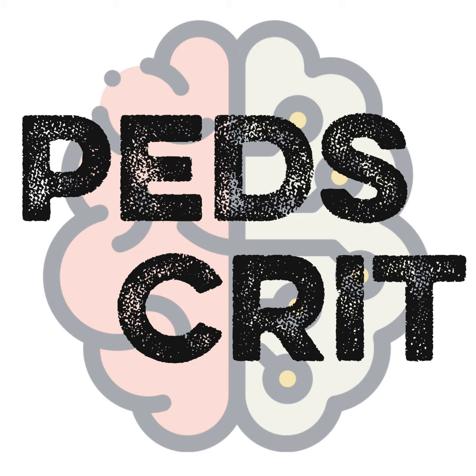It is so hard to make a generalization because every patient can be a little bit different. I still always try to look at trigger first and make sure our trigger is right, because the patients you just mentioned may have multiple reasons to not have the best trigger sensitivity. So if they have a trach, is it a cuffed trach or not? Is there a leak? So are we set up for trigger issues there? Even if they have a leak and are not auto-triggering, which is when we talked about a leak setting up your situation for auto-trigger, if they go to take a breath and they're getting some air around the trach as they inhale, the ventilator may not sense all that flow. And so the patient may actually be making a good effort and the ventilator doesn't sense the flow and so doesn't give them a breath.